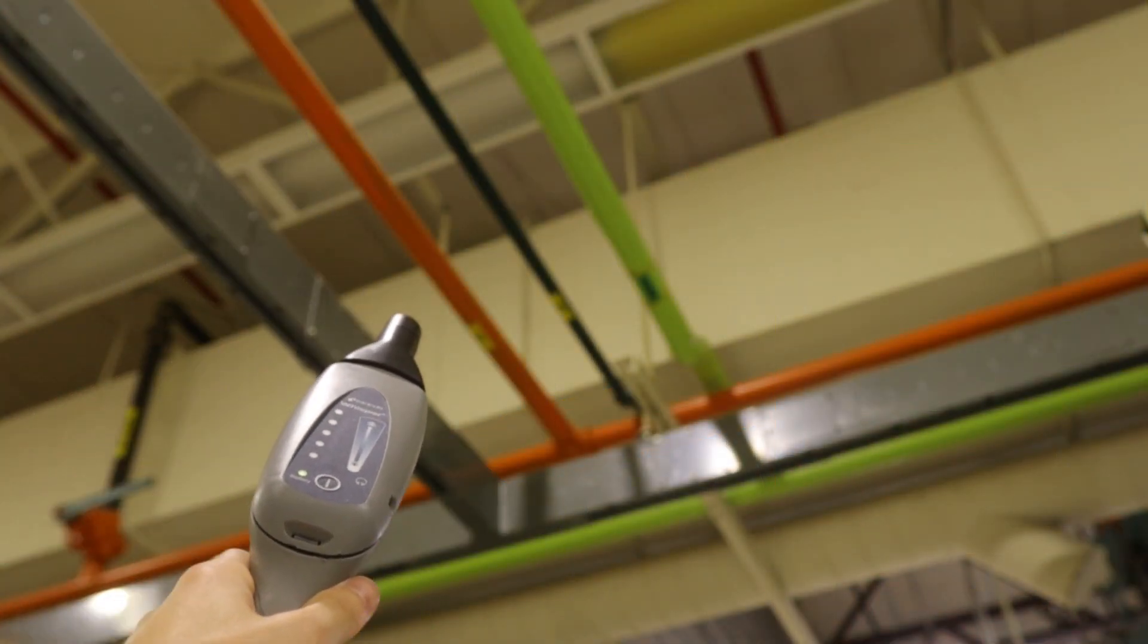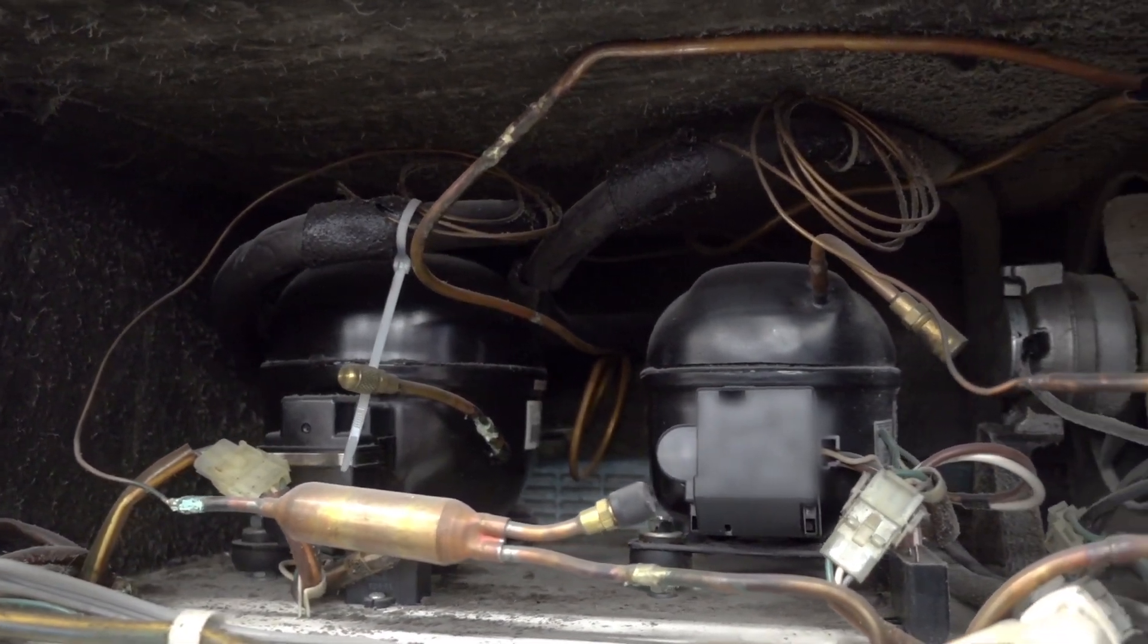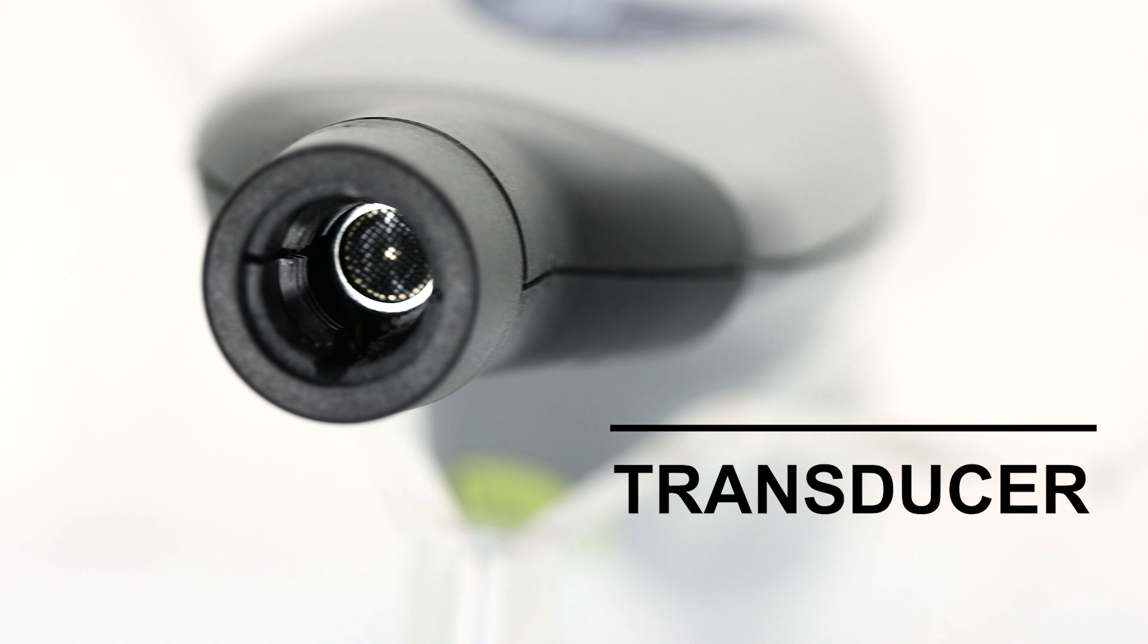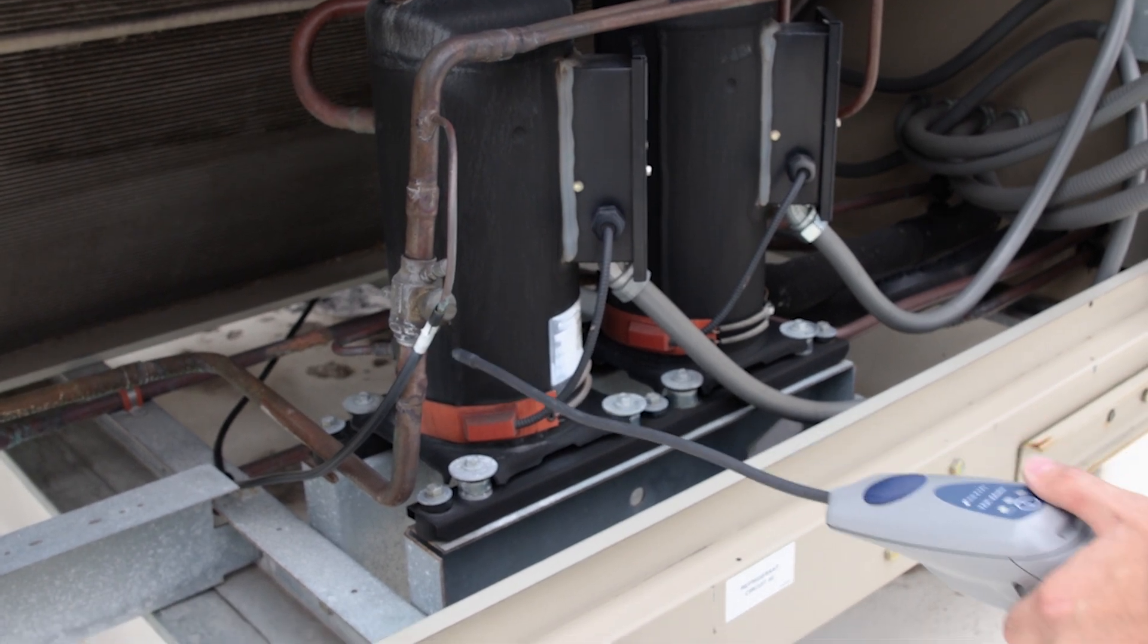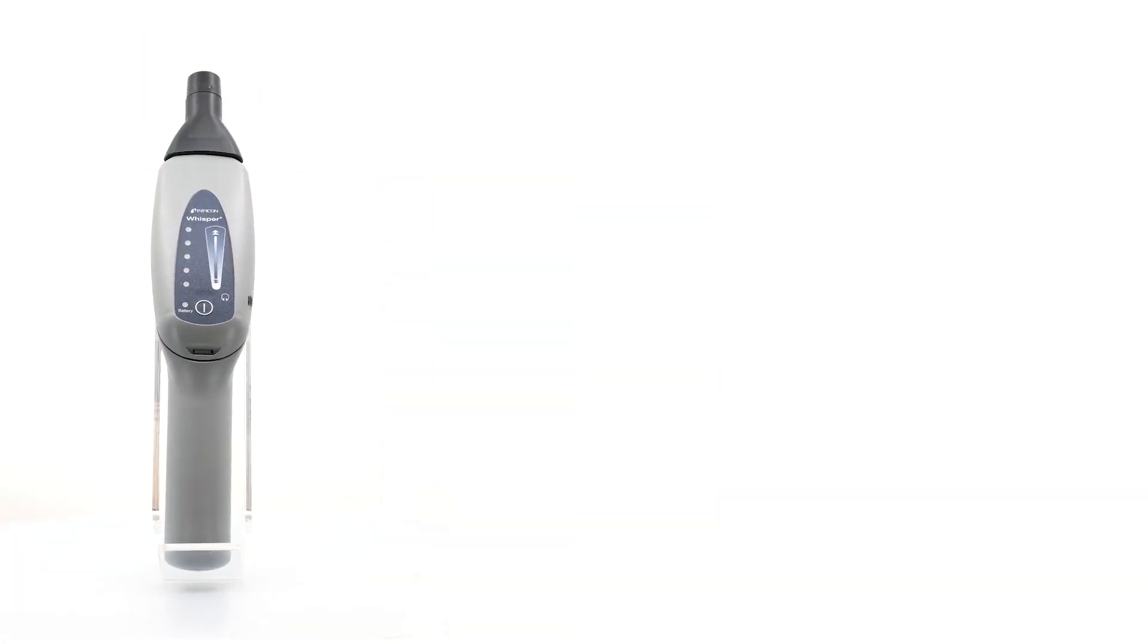That's where ultrasonic comes in. When a pressurized system, like an HVAC system, leaks, the escaping gas creates an ultrasonic disturbance of around 40,000 Hz. That's well outside of the human hearing range. Inficon's Whisper uses a specialized transducer designed to detect the frequencies emitted by those leaks. So instead of identifying the presence of refrigerant, like a traditional leak detector, you're using the ultrasonic leak detector to actually listen for the leak.